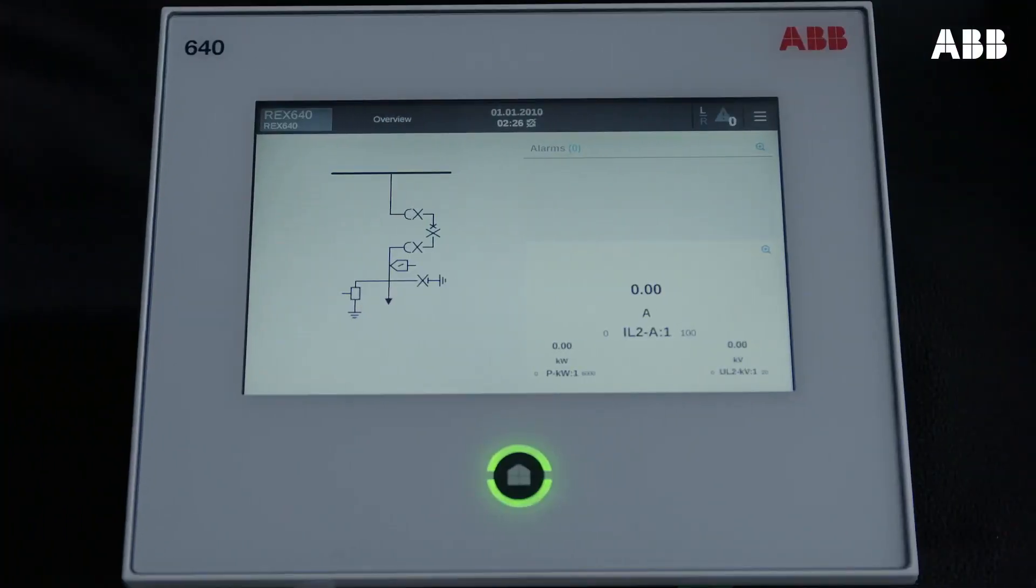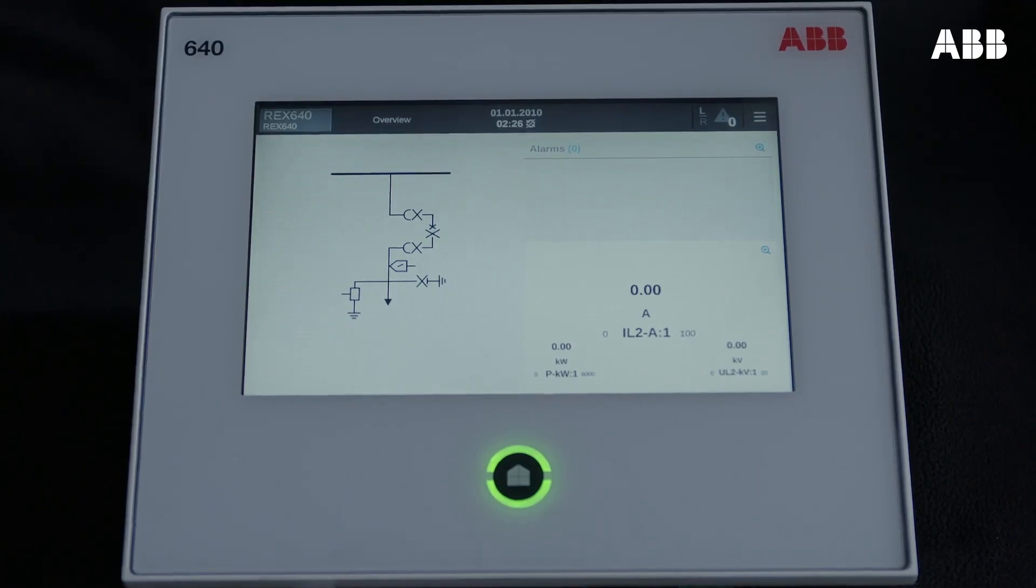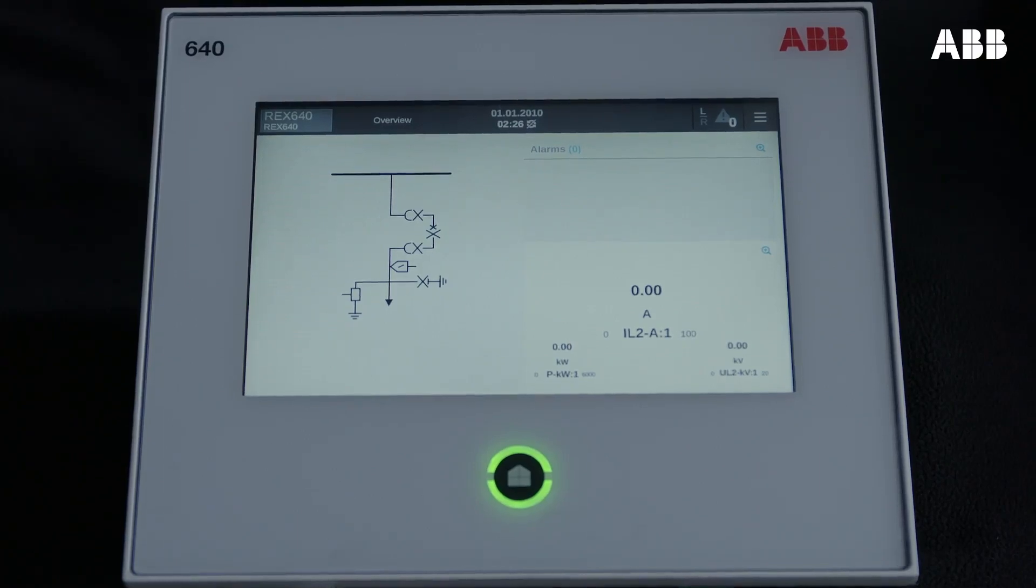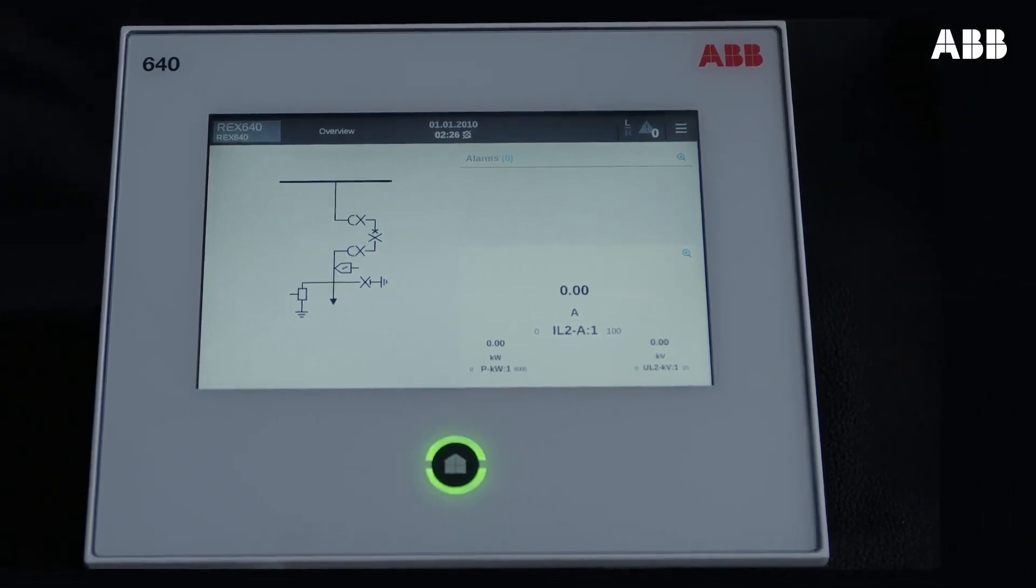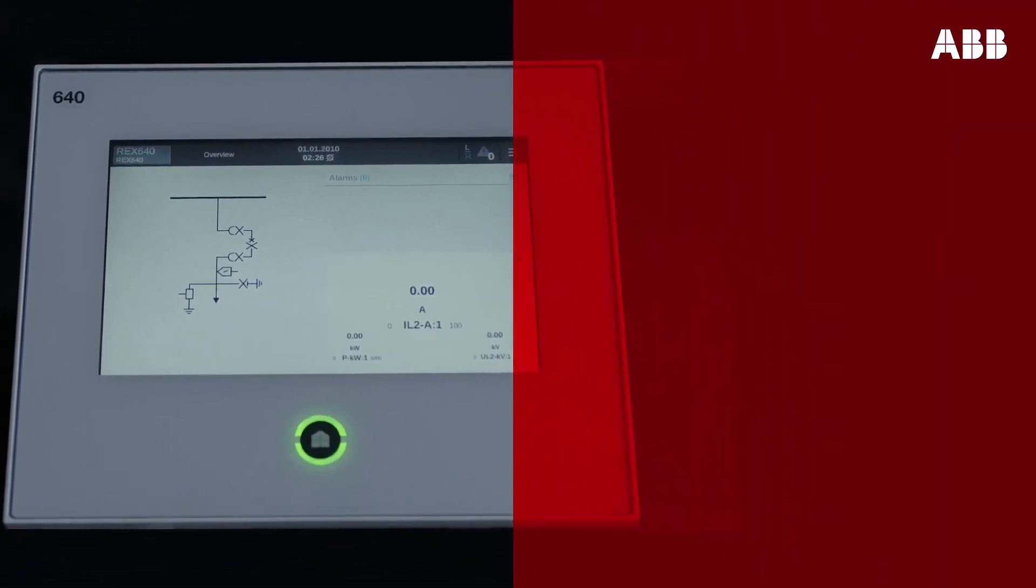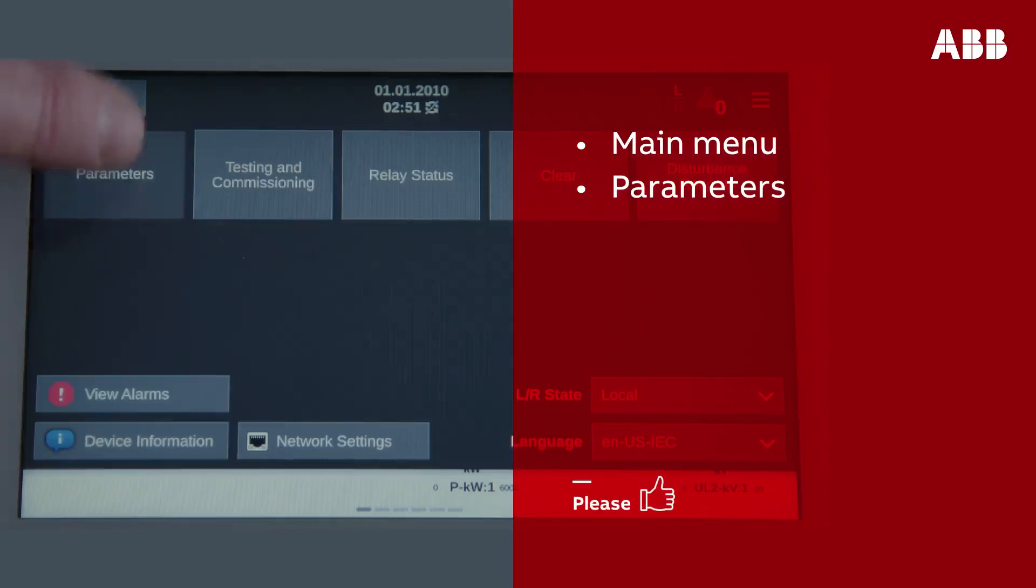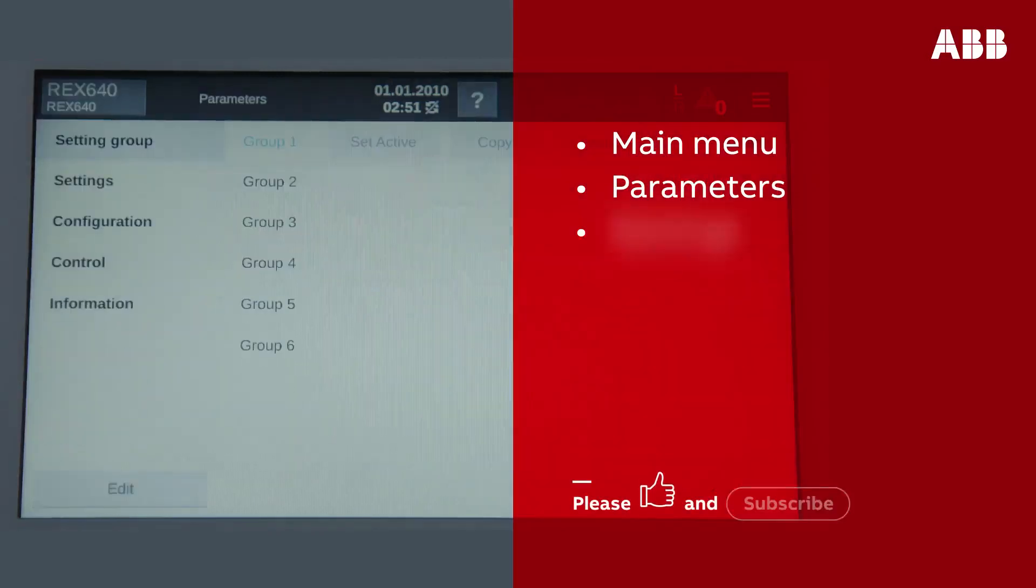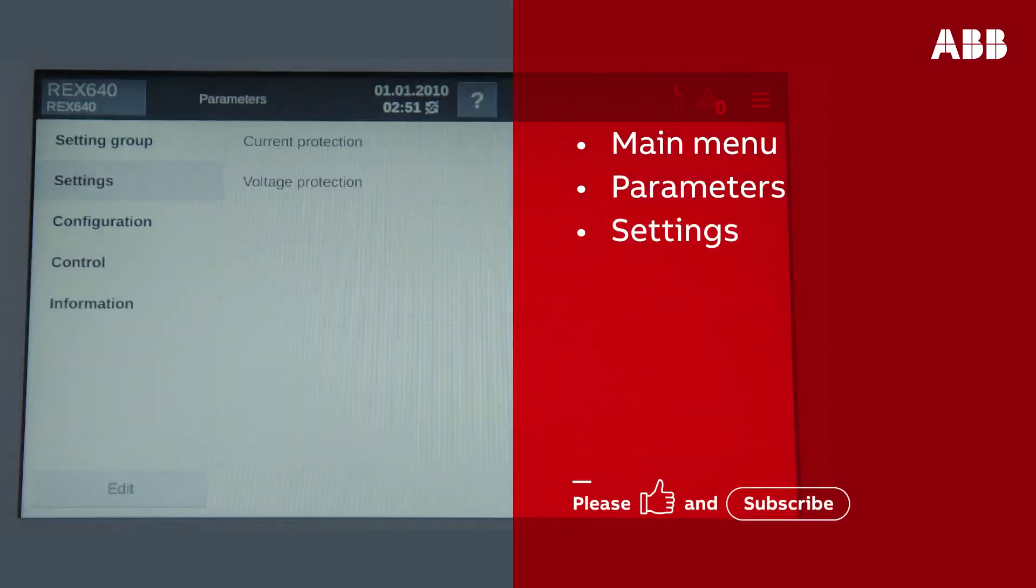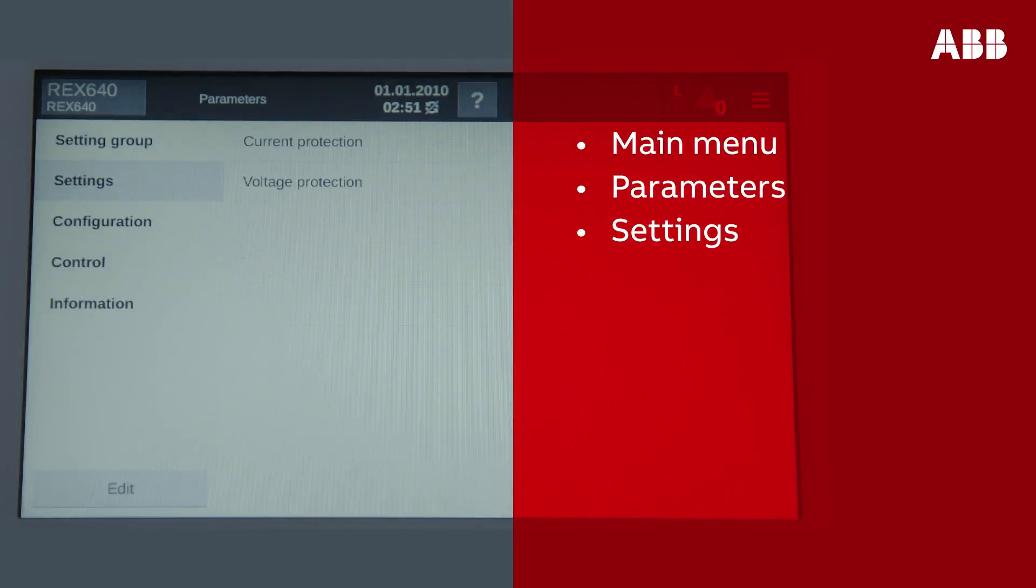Lastly, you need to verify the update on the relay's LHMI display. If it is updated, you will see the new functions appear in the menu. To check this, browse through the menu and select Parameters, and then Settings. Here you can see all configured functions listed.